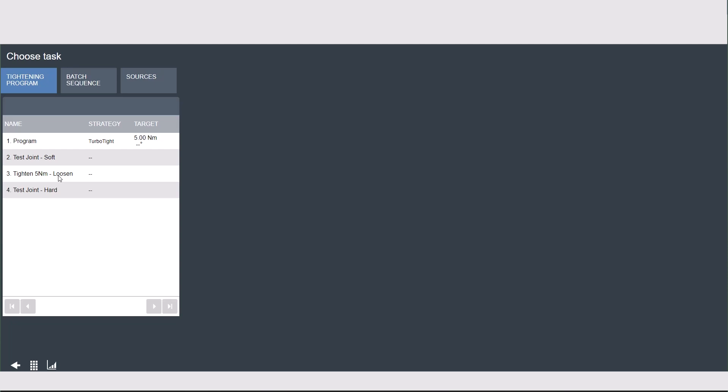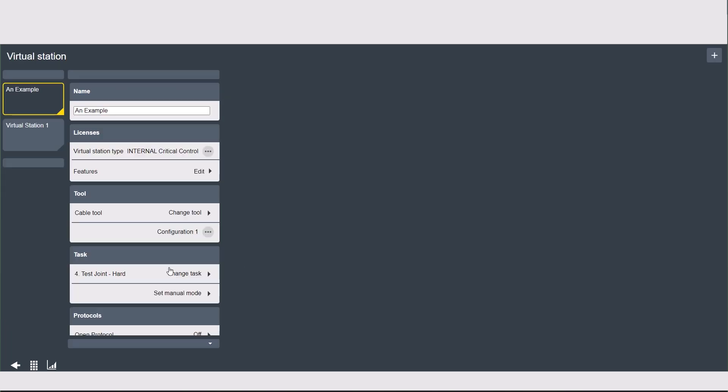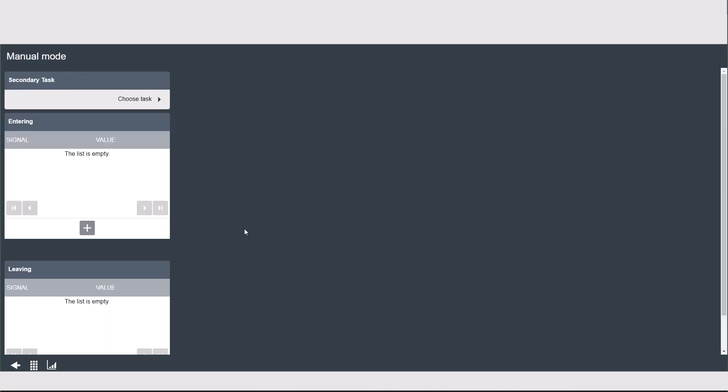There are going to be other videos about source selection for the PowerFocus platform that you can watch after this for more information. Once you select what you want this tool to run, it's going to show the name in the task tab. Underneath that is manual mode — or test tightening in the PF6 Flex. This is essentially a backup mode that can be triggered if the tool needs to perform work outside of its normal task — for example, if the tool needs to be calibrated over a lunch break or there's an issue with the MES system. Manual mode can assign a secondary task to run when triggered, and you can assign different entering and leaving signals. This setting is not widely used and can most often be left unconfigured. If you need more information about manual mode, please contact your local Atlas Copco representative.